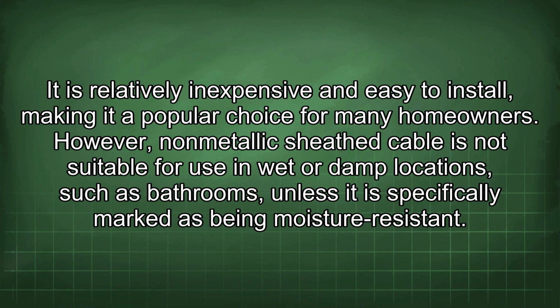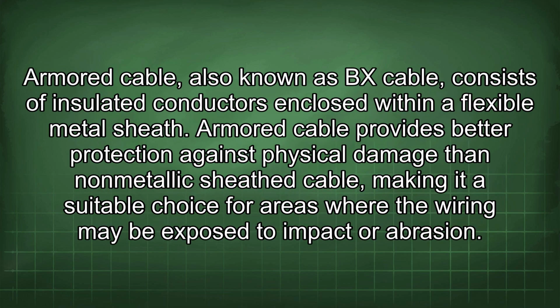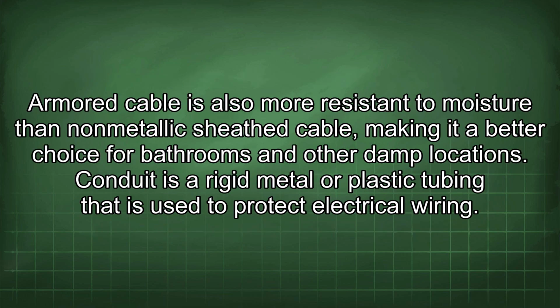However, non-metallic sheath cable is not suitable for use in wet or damp locations, such as bathrooms, unless it is specifically marked as being moisture resistant. Armored cable, also known as BX cable, consists of insulated conductors enclosed within a flexible metal sheath. Armored cable provides better protection against physical damage than non-metallic sheath cable, making it a suitable choice for areas where the wiring may be exposed to impact or abrasion. Armored cable is also more resistant to moisture than non-metallic sheath cable, making it a better choice for bathrooms and other damp locations.